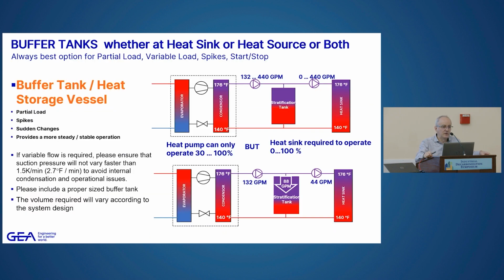Then, on integration, you always need to start thinking about using buffer tanks on your heat source and buffer tanks on your heat sink. A buffer tank is going to help a lot with heat pump operation. It's going to help you with partial loads, sudden changes, spikes, and any of these changes where you want to go from 100% down to 0%. Well, heat pumps go down to a minimum of 30%. If you need that 0%, use a buffer tank. And a buffer tank is going to give you operation without the heat pump for 1 hour, 2 hours, 3 hours. Always think about what your backup is when the heat pump is down, when the heat pump is not running. So probably it's going to be your buffer tank, or continuing to use your boiler, or putting in an electrical boiler.